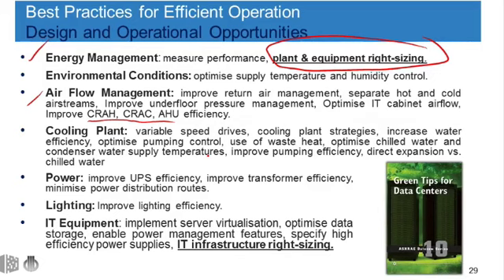I touched on waste heat opportunities earlier. The waste heat coming back from data centers is generally considered to be low grade, but there are opportunities to reuse it if the IT load does exist. And for example, I'm familiar with data centers with offices associated with those data halls where the waste heat's been used to preheat the fresh air during the winter periods. And there are other examples there of cooling plant, and as I said, there's a lot more detail within the book.